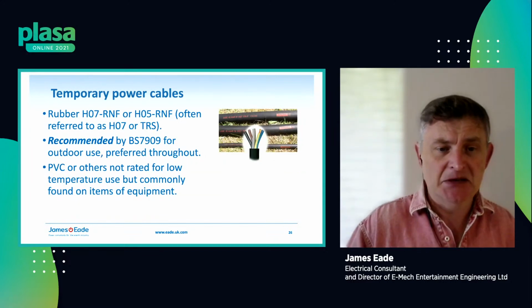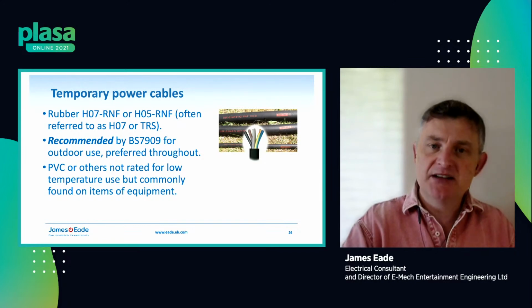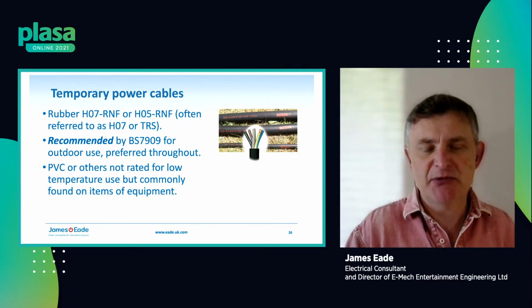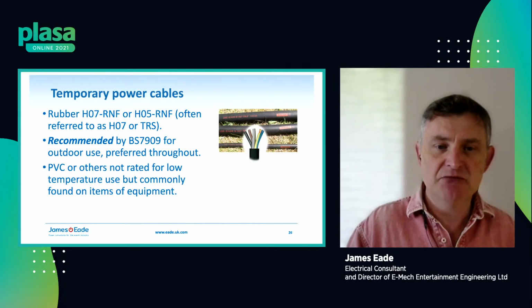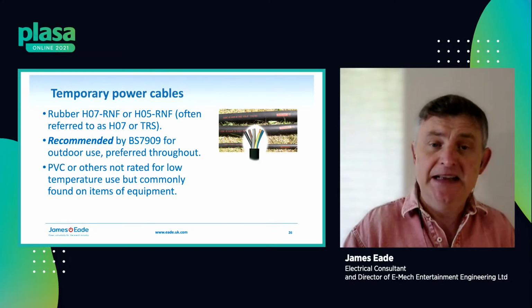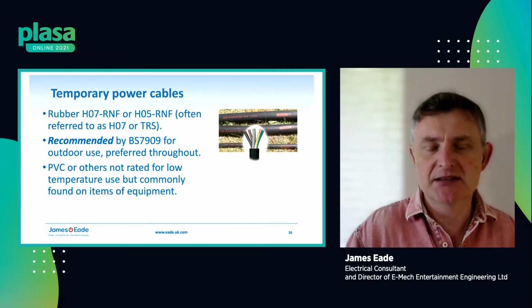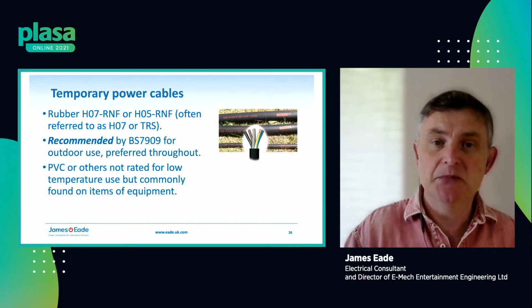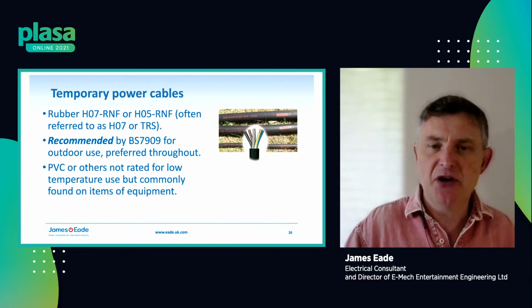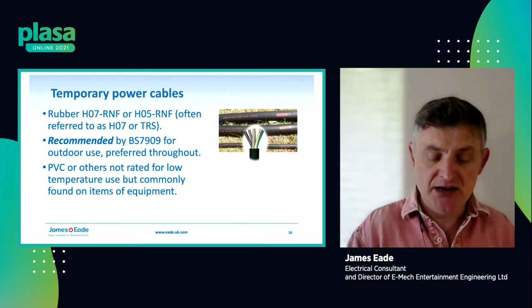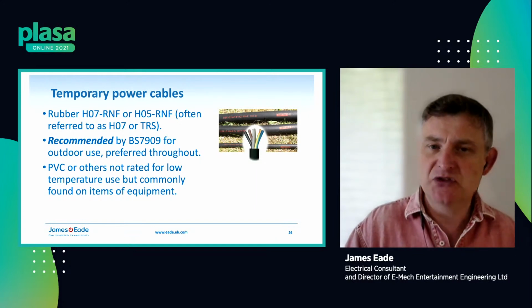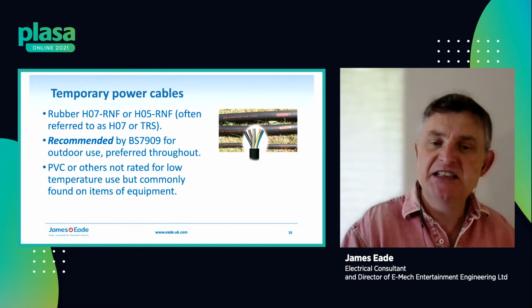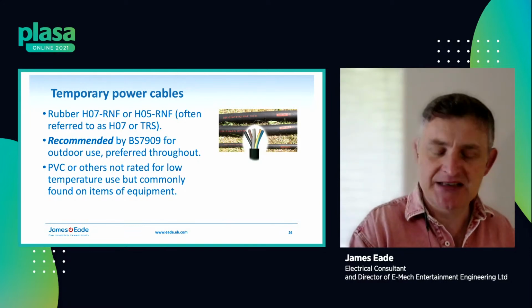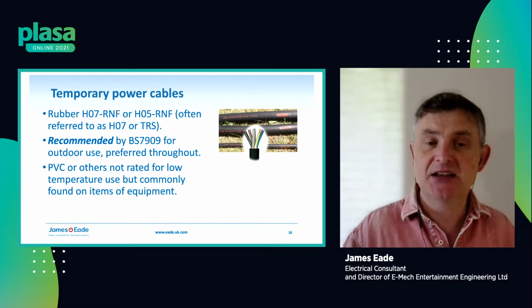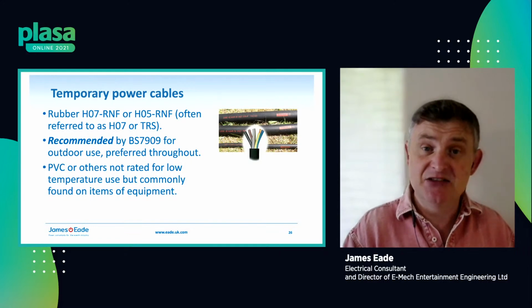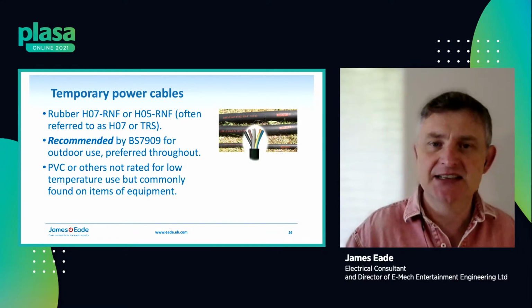So if we go to the next slide, just a bit on rubber cables. When you look at a bit of TRS, which is the old tough rubber sheath terminology, it's now known as HO5. The HO7, HO5 RNF is the harmonized designation that's common amongst cable manufacturers, stemming from European standards. And the 07 and 05 bit relates to the voltage rating of the cable. And the reason why HO7 is chosen is because it has a higher voltage insulation rating up to 750 volts. And we don't need the higher voltage rating, but the way manufacturers achieve that higher rating is to use thicker rubber. So HO7 is specified because the jacket has got more rubber and is therefore more mechanically resilient than, let's say, an HO5 one.